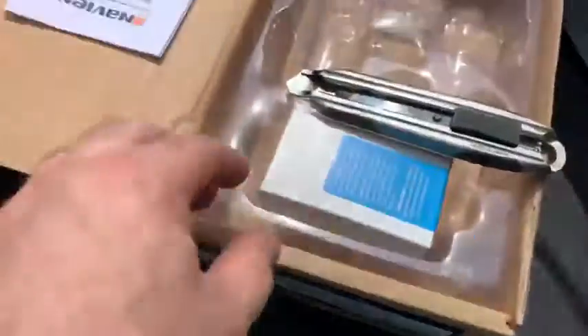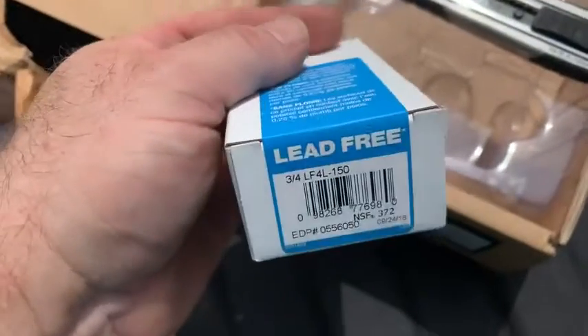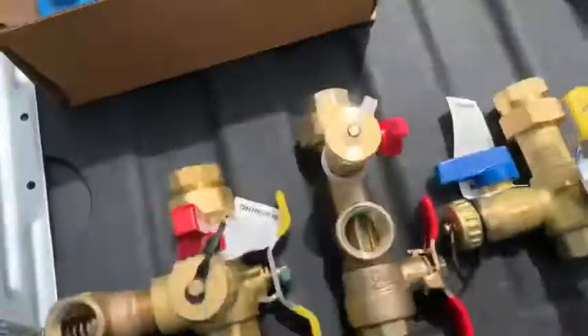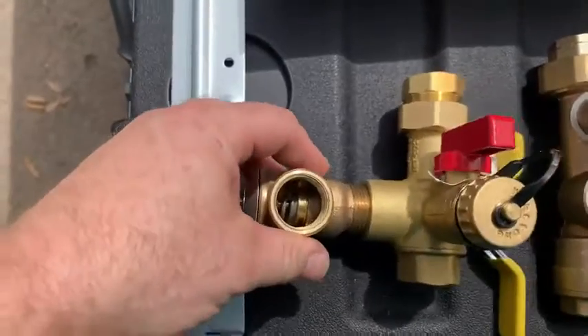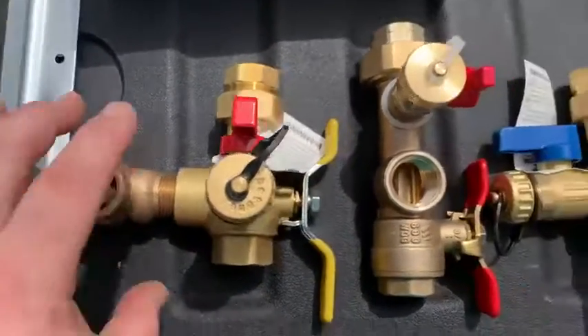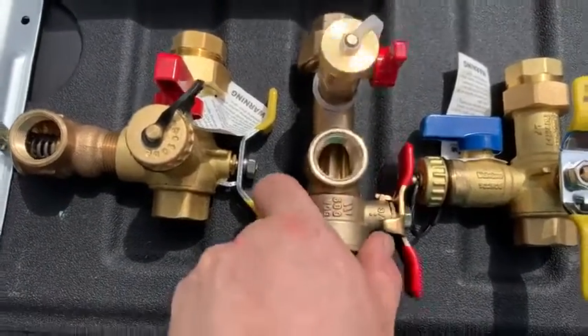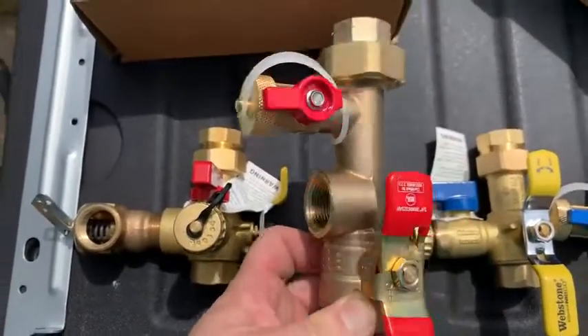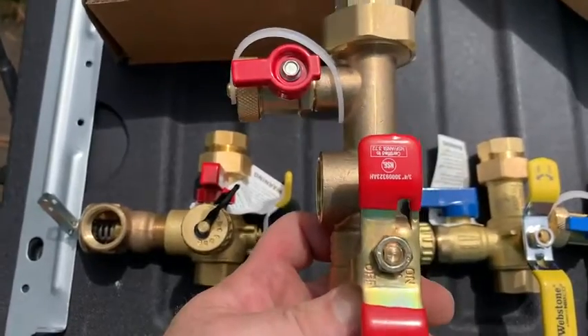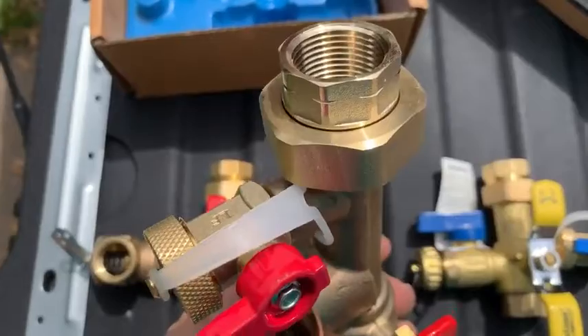Hot side now. Watts ships the relief valve in a box separate in the packaging, and Webstone does also — I've threaded it in here just to show you the difference. The relief valve on the Watts slash Navien Plum Easy valve threads into that three-quarter inch port. You've got a red handle to signify the hot side and an o-ring seal on a union nut.